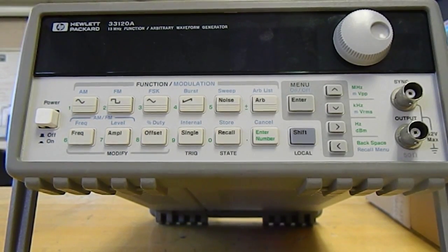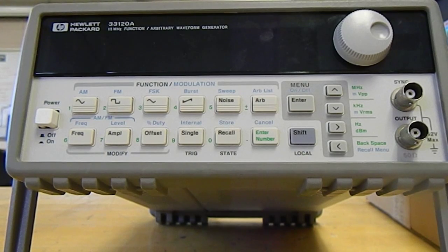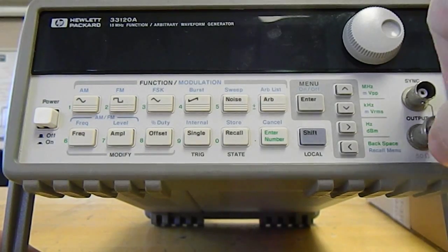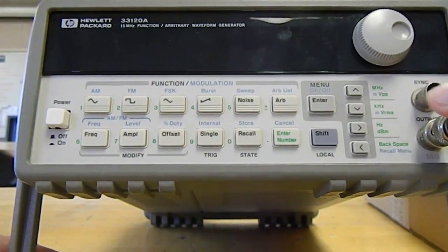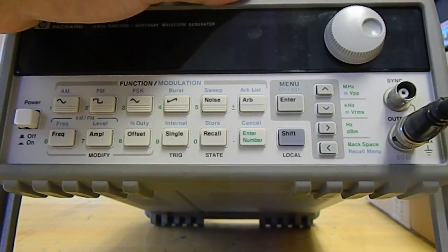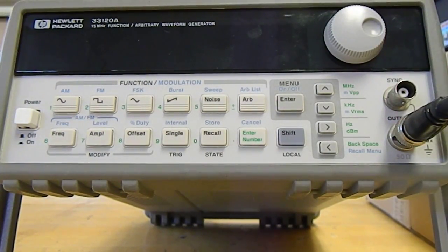This is an instructional video for an HP 33120A function generator. The first thing you need to do is make sure that the function generator is connected to power, and then you can connect the output. You can see this is output of the function generator via BNC cable to whatever circuit or device you're using this with.